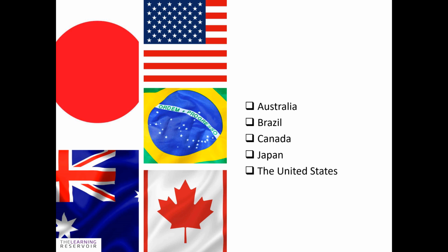So if you are selling your medical devices into each of those markets, if you're not participating in the MDSAP and have that program in place, you would have to have separate audits by those 5 different regulatory authorities that are in those countries. But if you participate in the MDSAP program and implement that MDSAP program in your company, that eliminates the need for having 5 separate regulatory audits from those different jurisdictions. You just need to have one, which is fantastic.